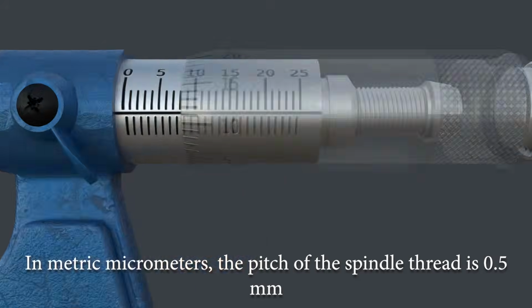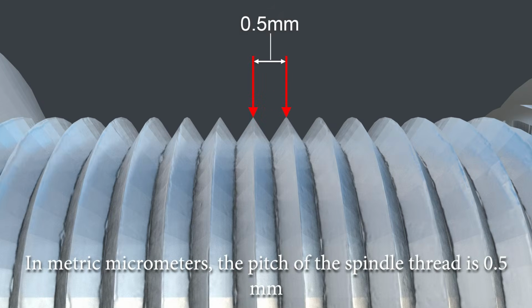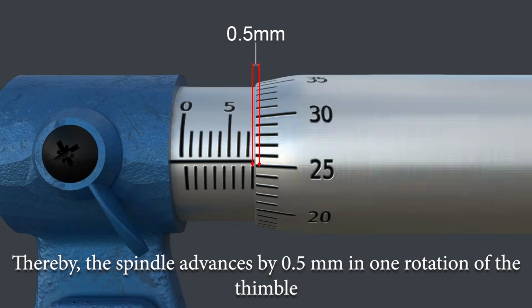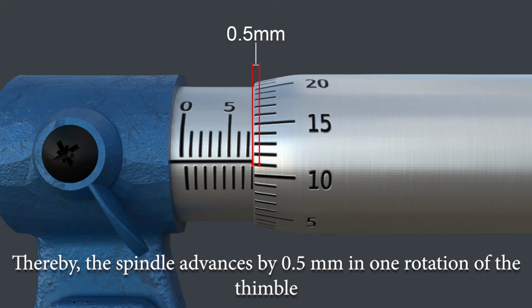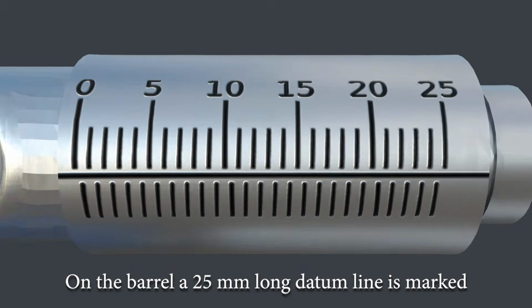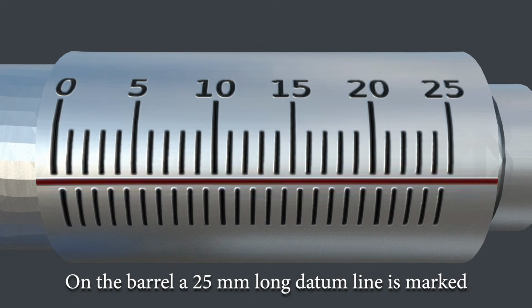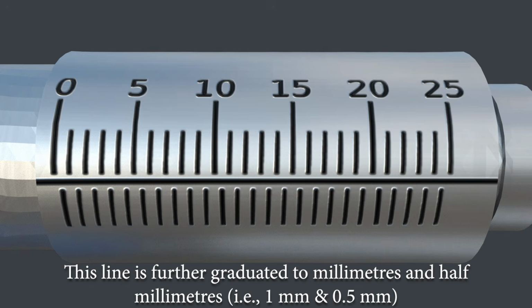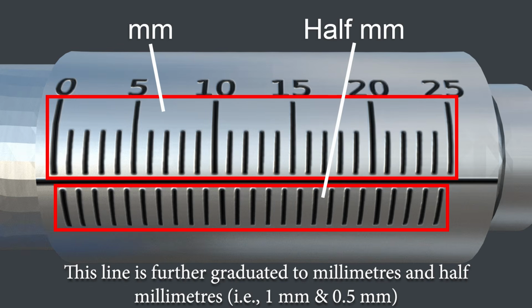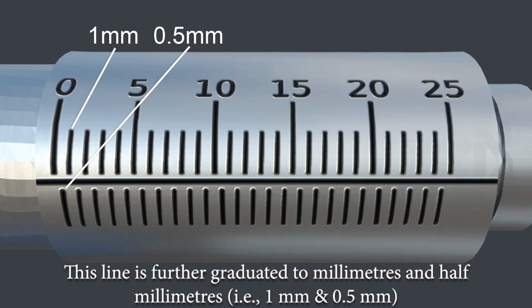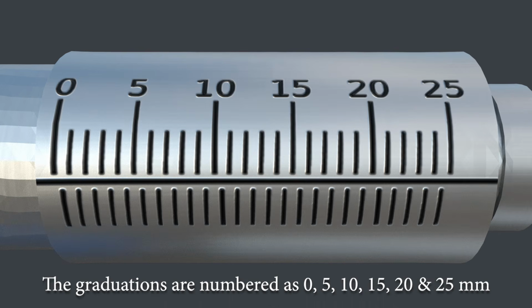Graduations. In metric micrometers, the pitch of the spindle thread is 0.5 mm. Thereby, the spindle advances by 0.5 mm in one rotation of the thimble. On the barrel, a 25 mm long datum line is marked. This line is further graduated to millimeters and half millimeters, that is 1 mm and 0.5 mm. The graduations are numbered as 0, 5, 10, 15, 20 and 25 mm.